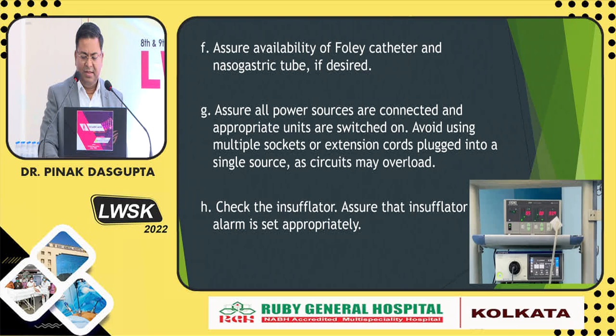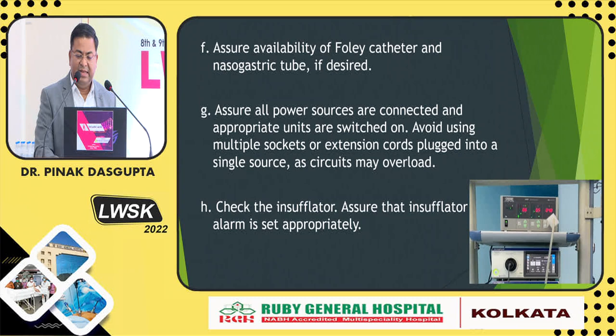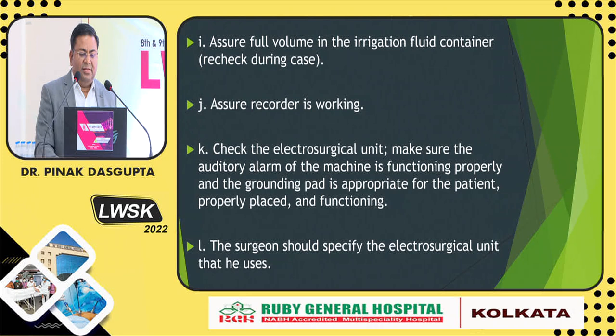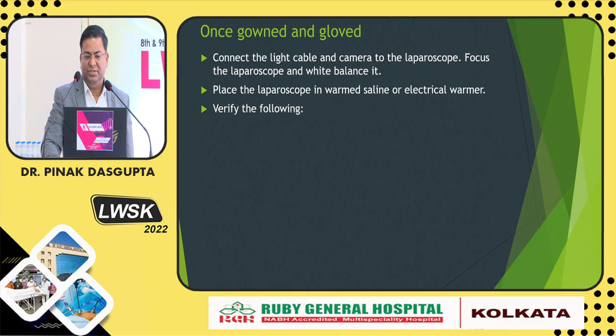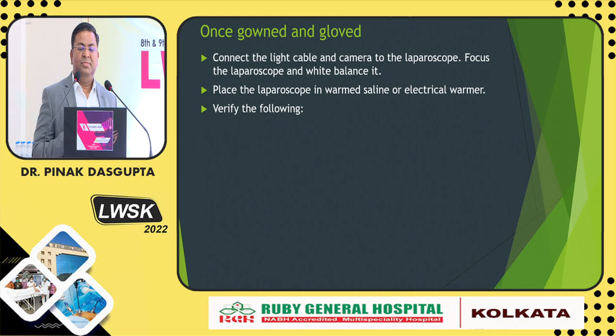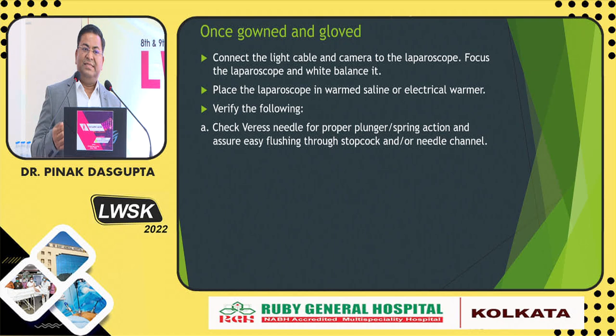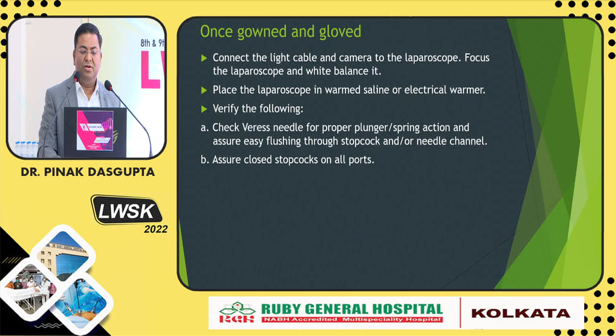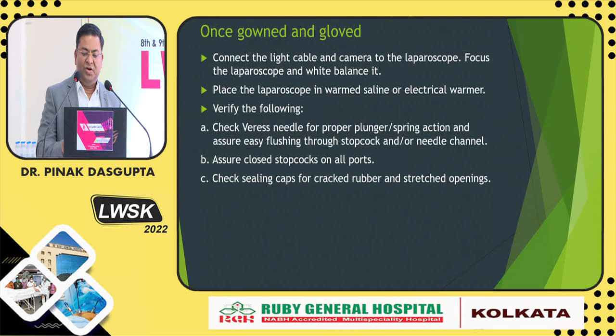But still, before starting the procedure, someone has to check that everything is in place and functioning. Once you are gowned and gloved, you should check that the light cable is connected, the camera processing unit is appropriately plugged in, and the saline irrigation system is functional. You should check the Veress needle before inserting it, to see whether the spring action is functioning, and check the valves for whether they are open and whether there is any leak in the washers. All these things have to be checked before you actually start the procedure.